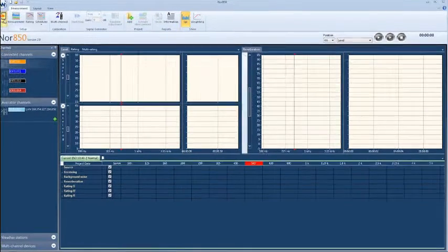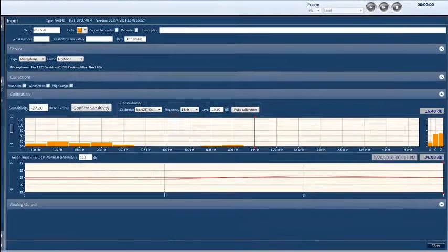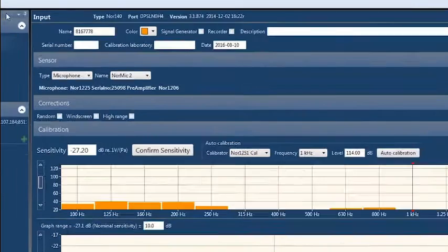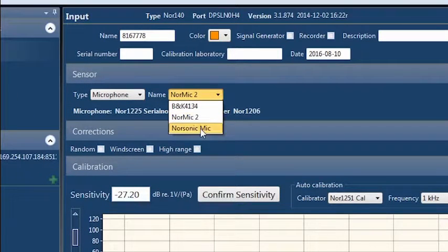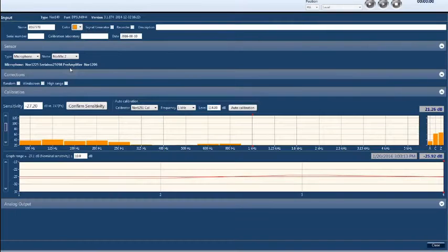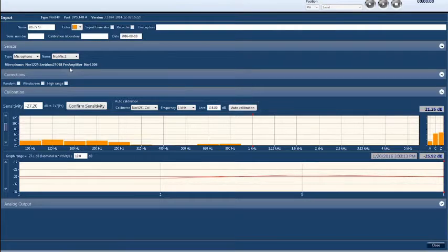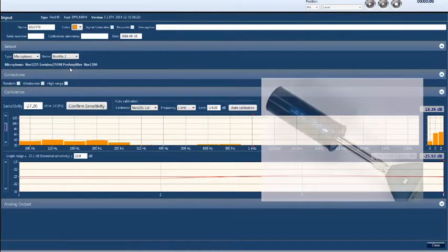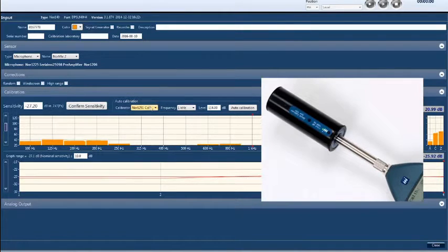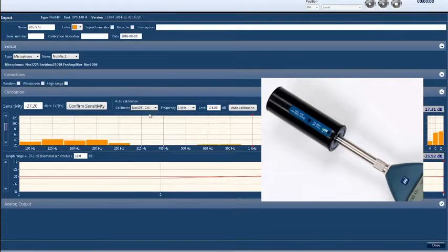Once entered into the database, the sensors are available in the input menu of each measurement channel. This menu also provides the option to verify the sensitivity of the sensor by calibration. For example, the sensitivity of a microphone can be automatically verified by attaching a calibrator with a reference signal, such as the Norsonic NOR1251 calibrator with a 114 decibel reference signal at the 1 kHz frequency from our sensor database.